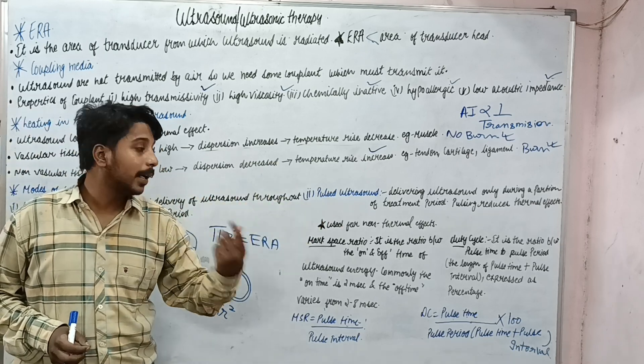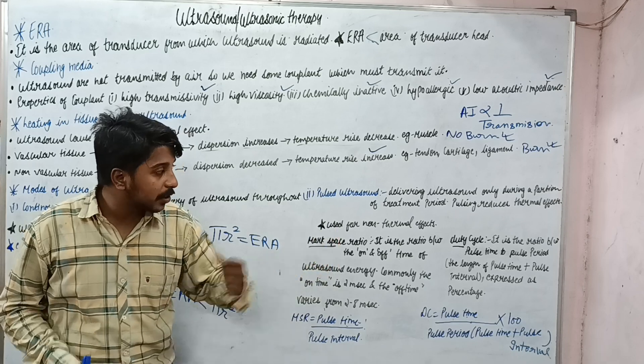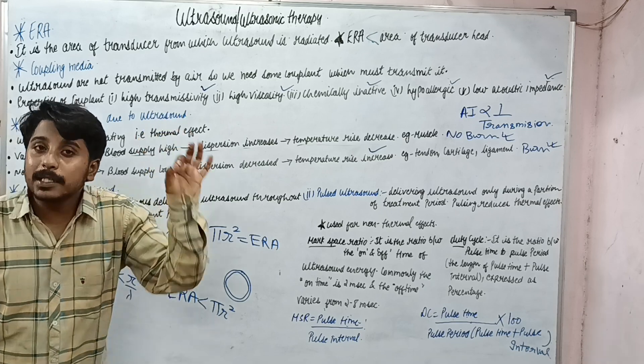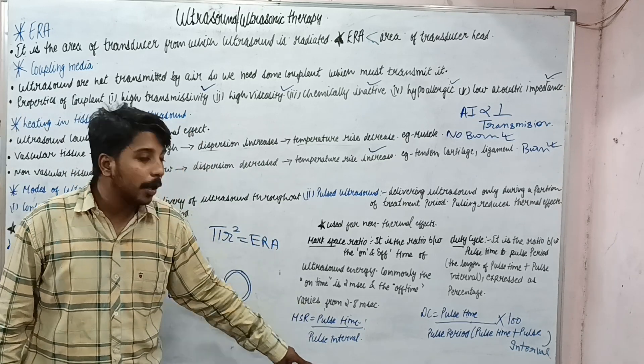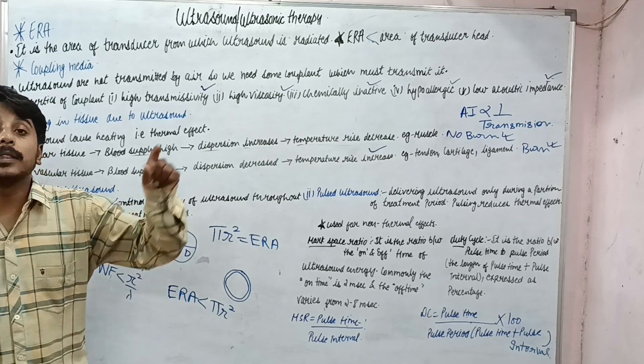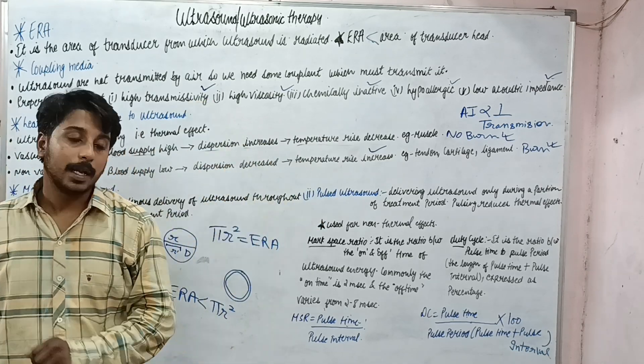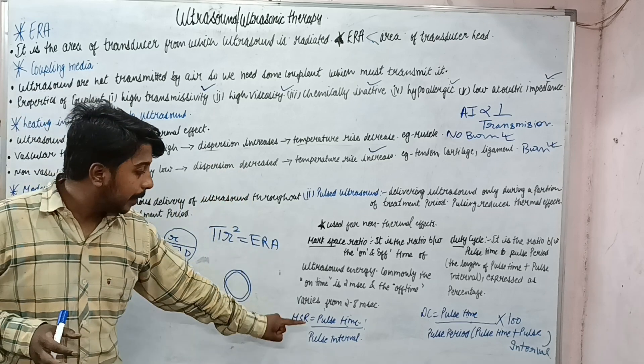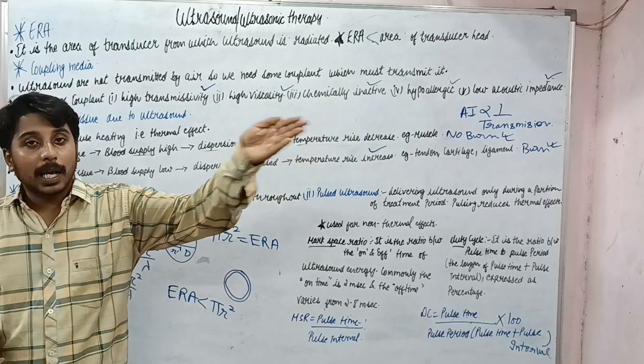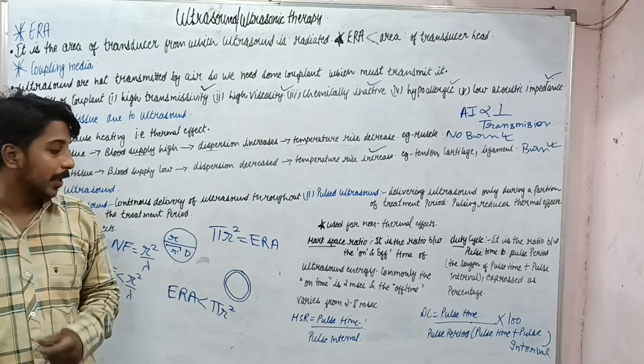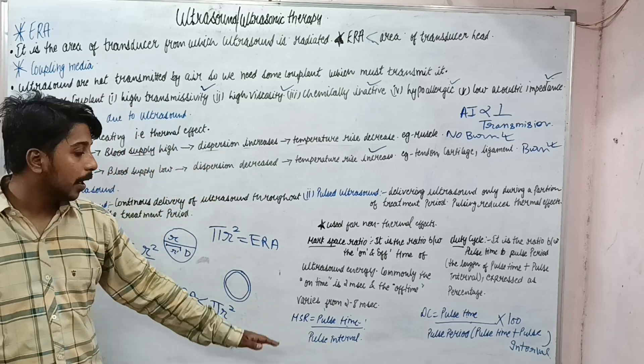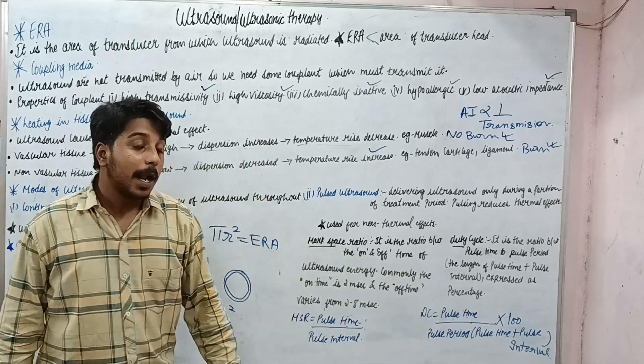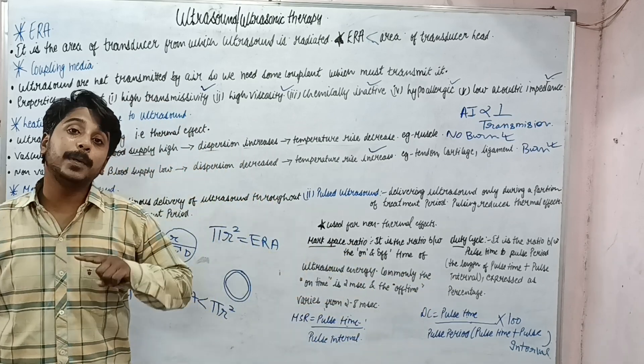In pulsed ultrasound, you need to understand two things: first is mark space ratio, and second is duty cycle. Mark space ratio is the ratio of pulse time upon pulse interval. Pulse time is the time for which the ultrasound pulse is coming; pulse interval is the time for which the ultrasound wave is not coming. So it is: time wave is ON divided by time wave is OFF.